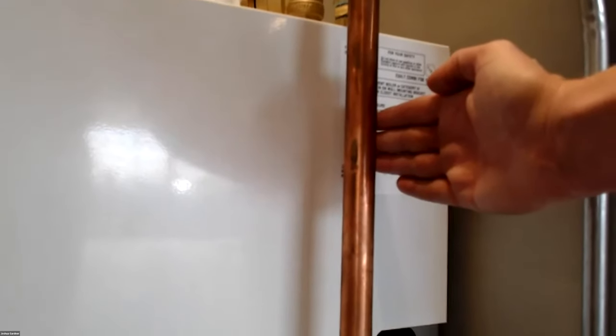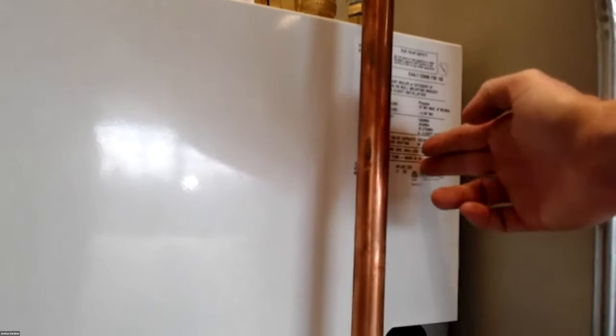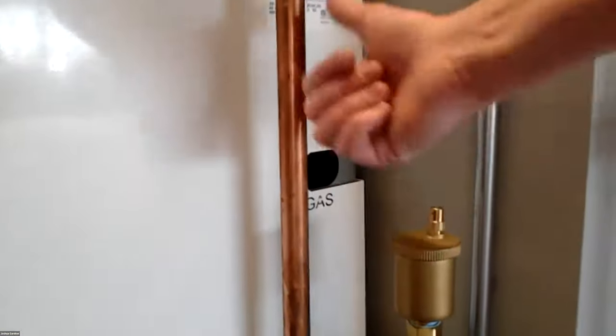Josh, inside the boiler, can you show the internal piping for the alternate left-hand connections? No, I can't. And that is because if you look, this cavity behind here is open right here. The back of the boiler is like right there. There's an open cavity here where that piping is. It just comes up from the bottom, circles up, and then tees off this way and tees the other way. So you can't actually see that piping back there. That's the back, but that's the other side.